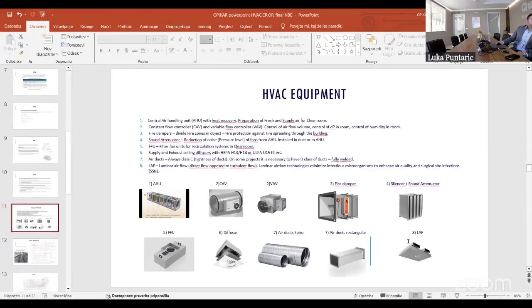Here are some of the most important HVAC elements that we use for our projects. On picture number 1, you have a central air handling unit. This is for preparation of fresh and supply air for the clean room area. On picture number 2 we have the constant flow volume flow controller and the variable volume flow controller. With them we control flow volume, differential pressure in the room, and humidity. We have fire dampers, which divide fire zones in a building and protect against fire spreading through the building.